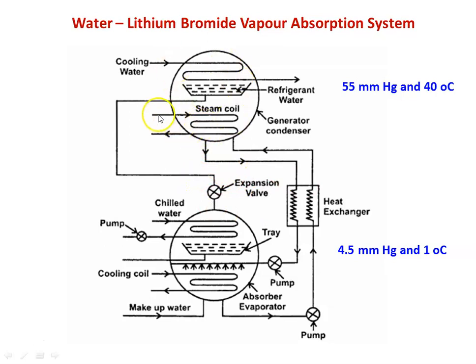Starting from the generator-condenser cylinder, there is a steam coil that heats the lithium bromide and water solution, producing water vapor. The generator produces water vapor, which moves up in the cylinder. A cooling water circuit with a condenser coil is present; when water vapor falls on the condenser coil, it is condensed and the condensate is collected in a refrigerant water tray. The refrigerant liquid water then flows to the absorber through the expansion valve, where pressure is reduced.